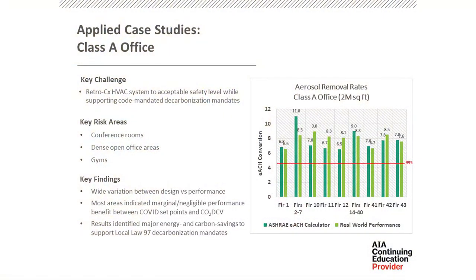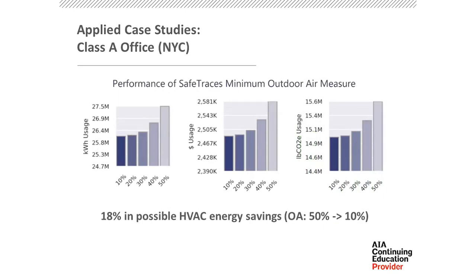So at the end of the day, what was the value of this? We were able to quantify the difference between design and performance. We showed that running the buildings back on CO2 demand controlled ventilation was fine, giving equivalent performance in terms of particle removal. We also found big potential energy and carbon savings to support the code mandates, potentially 20% savings in this building. So it's meaningful, it moves the needle.